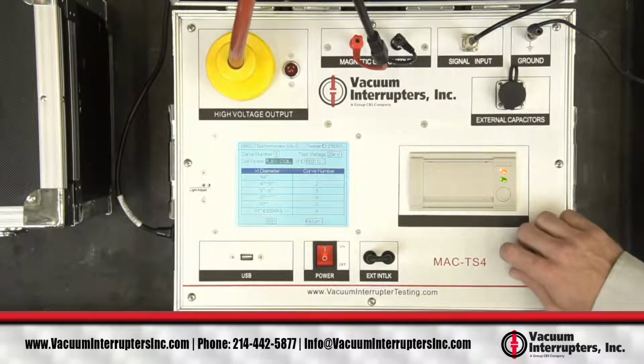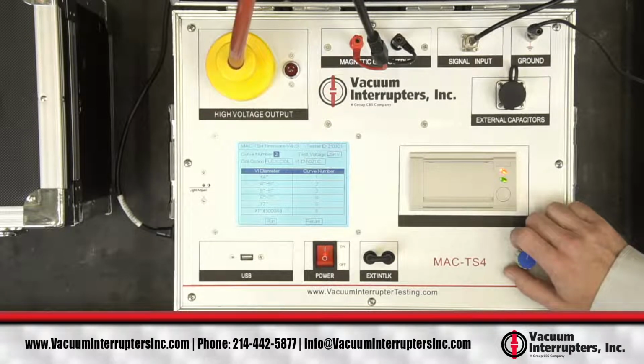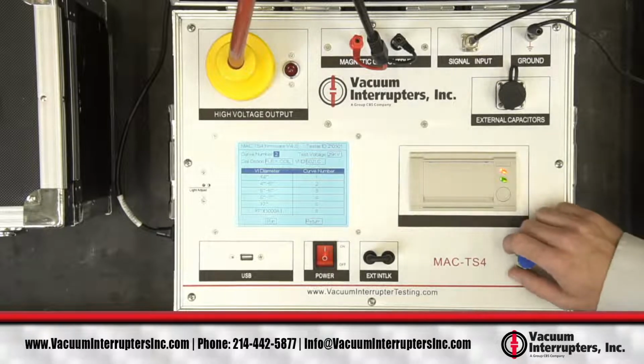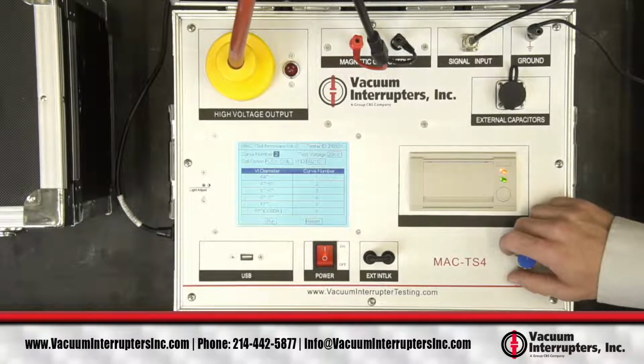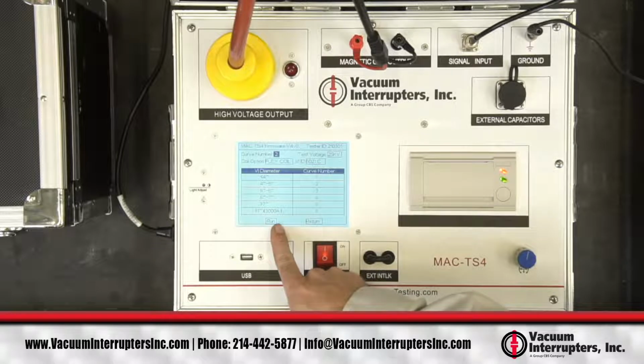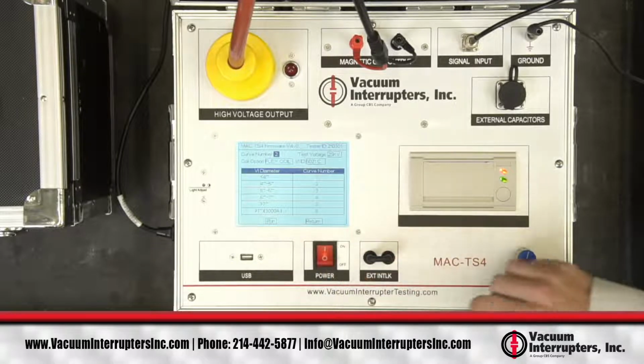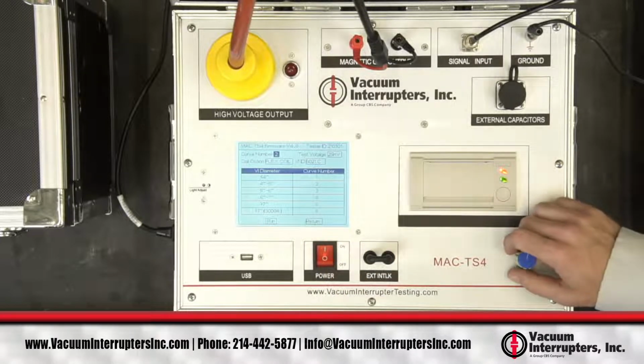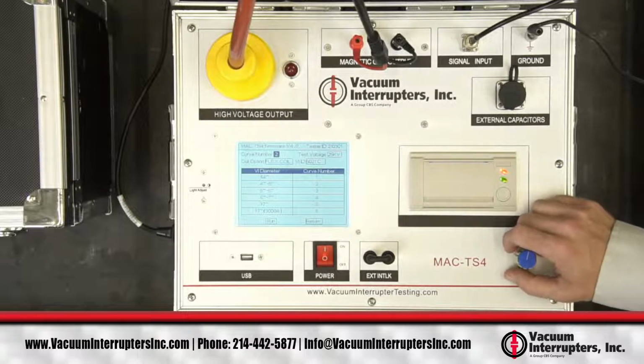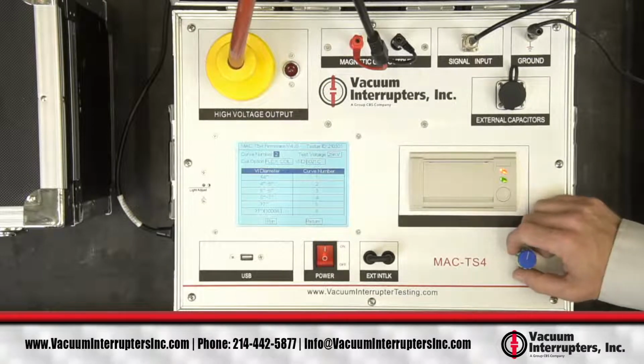Like I mentioned, there are different curves for the different vacuum interrupters. So you can see the different diameters of the vacuum interrupters and the curve number you should select for that diameter. These are approximately 4.5 inches in diameter, so I'm selecting curve 2.